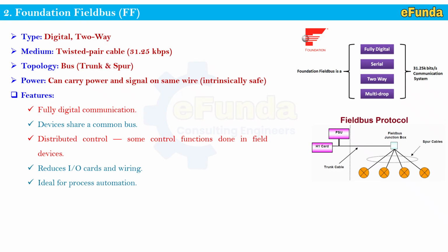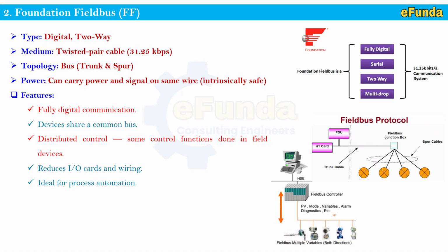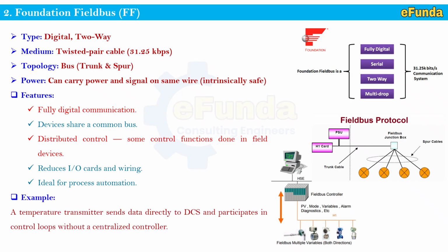One can refer to the architecture where fieldbus multiple variables in both directions are connected, starting from the field devices, which are connected to the H1 card, where PV, mode, variables, alarm, diagnostic, etc. information is transferred to the fieldbus controller, and then further it is connected to the operator console. Example: a temperature transmitter sends data directly to the DCS and participates in control loops without a centralized controller.